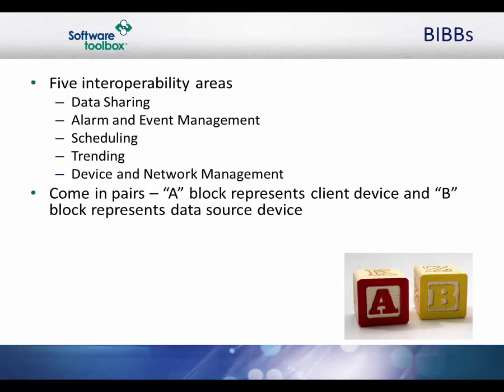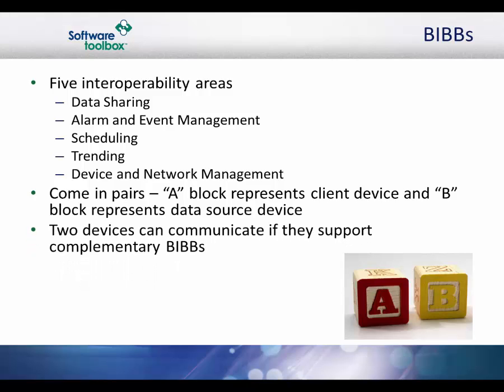BACnet interoperability building blocks, or BIBBs, come in pairs designated A and B that reflect the client-server nature of control system communication. The A BIBB represents the client or device that is trying to obtain information or command an action. The B BIBB represents the server or device that provides the data or carries out the command. If two devices support complementary BACnet capabilities — the A and B side of the same BIBB — then they are interoperable from the standpoint of that function. The basic idea is that for each kind of device included in a specification, the functional areas they need to support are selected, and BIBBs that apply to that functional area are chosen to match the level of desired sophistication.